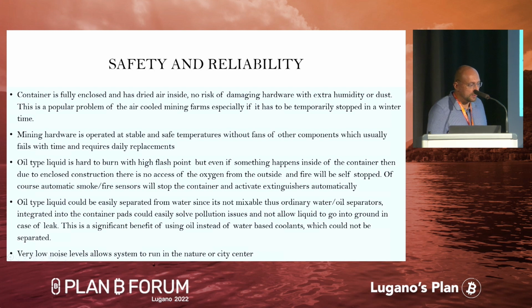This is one of the biggest benefits of this technology over others. Since all of this equipment is below the level of the liquid, it doesn't contain any rotational parts like fans. With ordinary air-cooled farms, all of these fans fail, and if you have thousands of units, you need a team of people walking every day replacing fans that aren't working. In our case, we have no parts that can potentially break, and the temperature of the liquid stays the same, because we can adjust it with the external cooling system accordingly. This means the hardware will be in a much more reliable state, because thermal expansion of the circuit board no longer exists. This is one of the reasons for failure of miners.